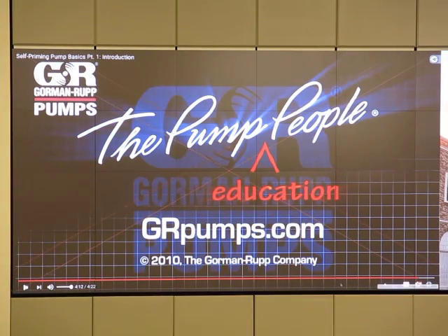So for the self-priming pump, you cannot start dry. It has to have some liquid inside to begin with, right? If you don't have any liquid to begin with, you cannot create vacuum. So self-priming means initially you have some liquid inside, you turn on the pump, it acts as a separator. It pushes some air out, and that liquid also goes up and comes back, and you create a vacuum. Because of that vacuum, then we can suck liquid up to the pump and then pump everything out.